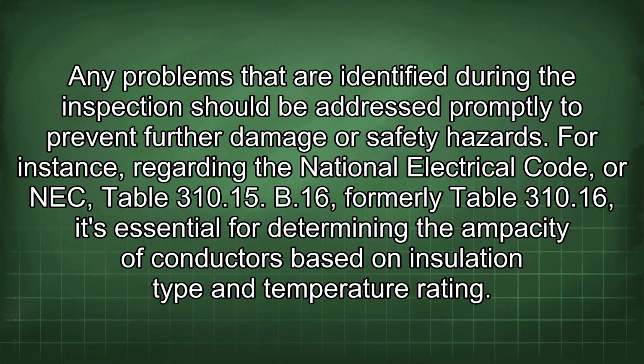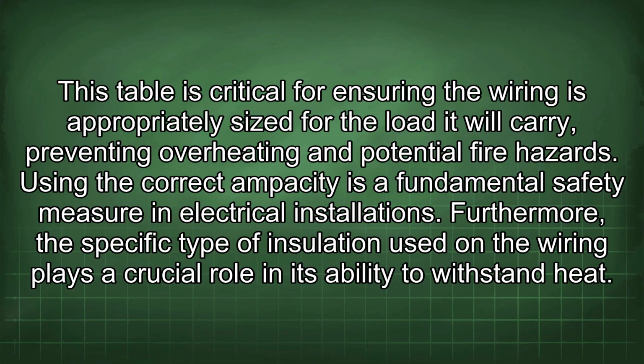For instance, regarding the National Electrical Code, or NEC, Table 310.15(B)(16), formerly Table 310.16, it's essential for determining the ampacity of conductors based on insulation type and temperature rating. This table is critical for ensuring the wiring is appropriately sized for the load it will carry, preventing overheating and potential fire hazards. Using the correct ampacity is a fundamental safety measure in electrical installations.